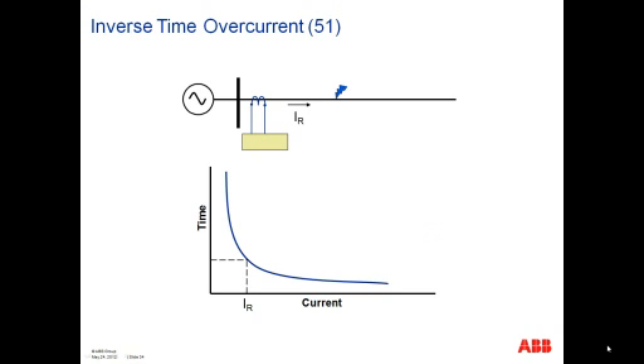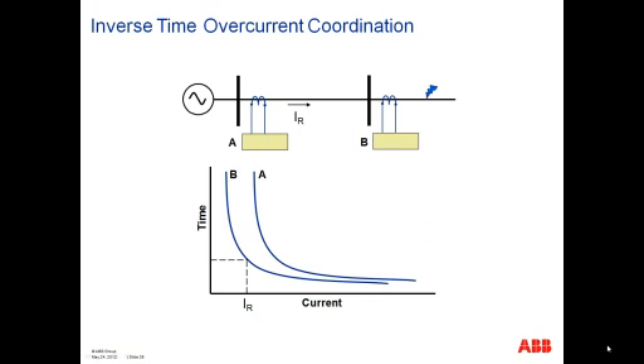Then you have the inverse time characteristic, such that the lower the current, the longer the time it takes to operate, and the higher the current, the faster the relay will operate with that inverse characteristic. And what that inverse characteristic is good for is to apply coordination. This will be covered in more advanced subjects, but basically, coordination with inverse characteristics allows the relay at B to operate first for a fault at the shown location before the relay at A operates.